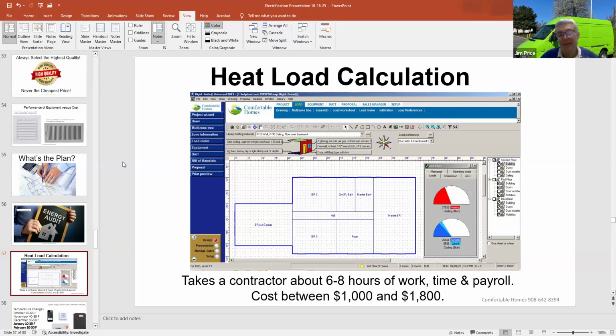They said the homeowner needed a bigger furnace or the same size, which was 100,000 BTUs. My load calculation revealed the house only needed about 27,000 BTUs. So we downsized to the smallest furnace the manufacturer makes, 50,000 BTUs. They were floored, asking how everyone else could be telling them they needed 100,000 BTUs and a 3-ton system instead of a 2-ton system.